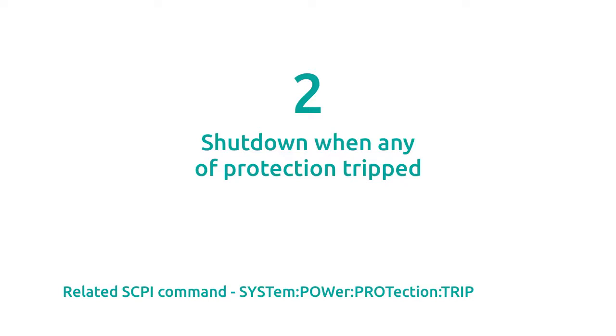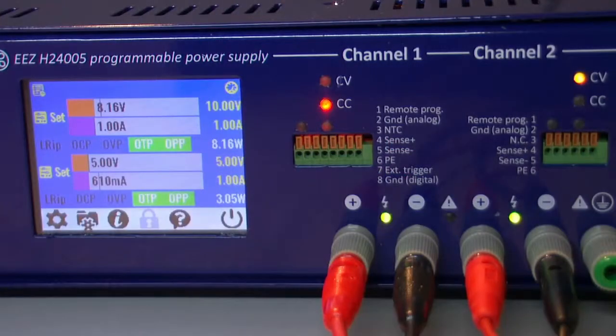Next protection mechanism is related to protection tripping. We have 4 different types of protections on each channel: over-current, over-voltage, over-temperature and over-power protection.